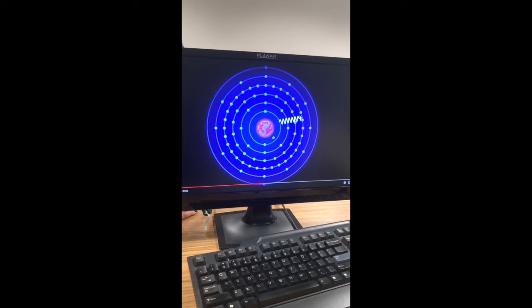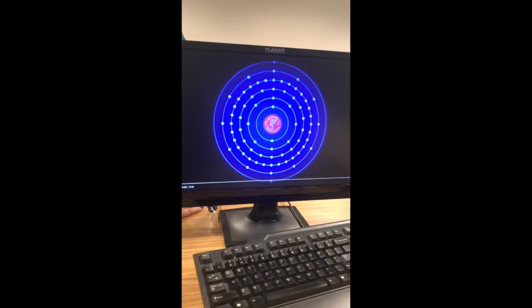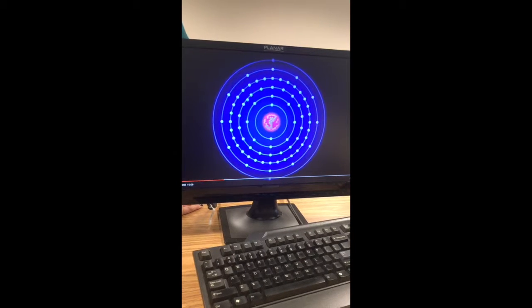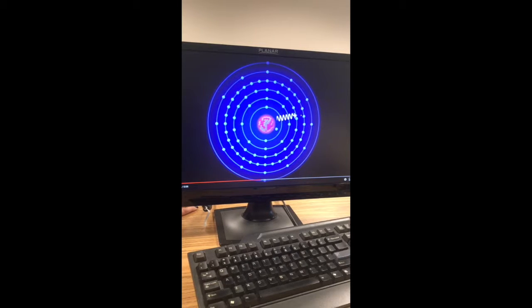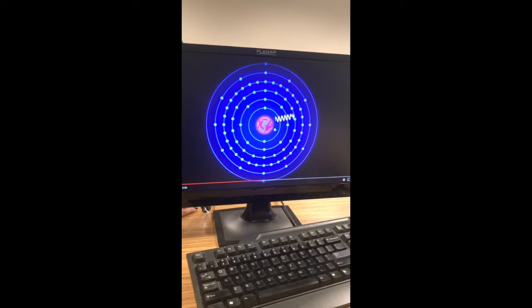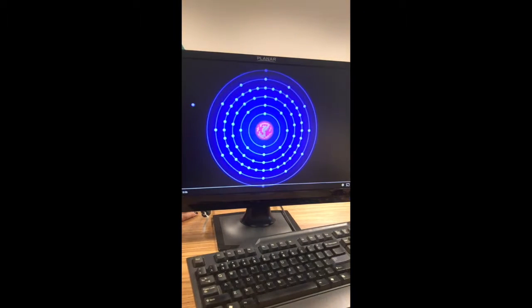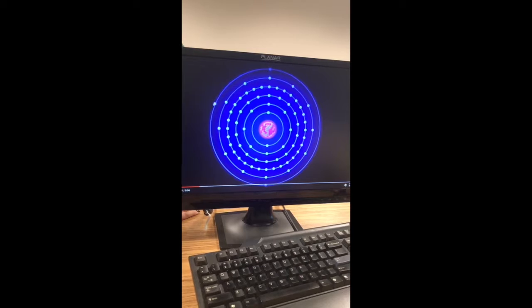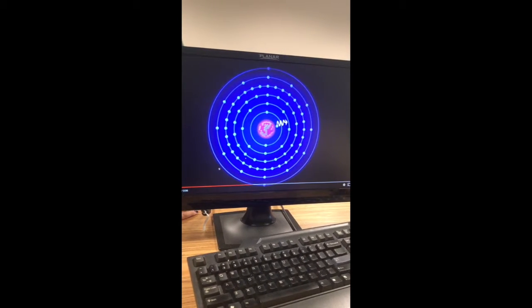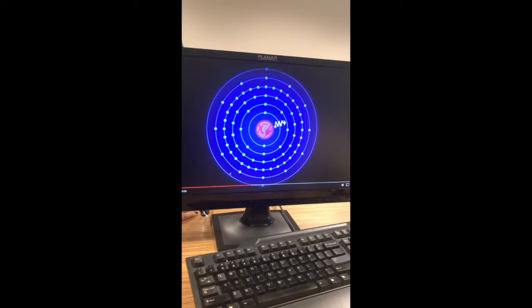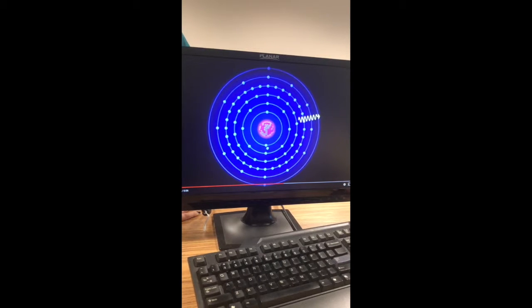Bremsstrahlung means stopped radiation. So this is actually related to the actions of the incoming electron that is braked and decelerated and produces the X-ray photon. So the energy of this X-ray photon is exactly the difference between the incoming electron energy minus the exiting kinetic energy of the same electron. For example, if the incoming energy of the electron is 100 keV and is braked or stopped, and this electron is exiting with 10 keV, the X-ray photon energy is a total of 90 keV.